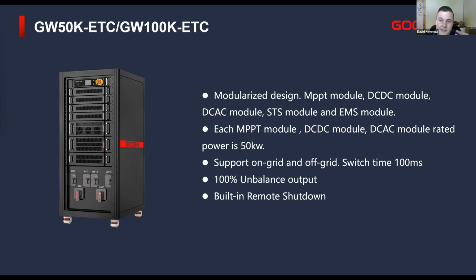These devices also have a lot of features and functionalities, from load management to that peak demand that I was mentioning earlier. We know that when customers are billed on kVA, that spike in peak demand normally increases their bill immensely. These devices are being designed to have that kVA compensation, so that even if you are saving your batteries for outages, it will use the batteries momentarily to mitigate that kVA demand and increase customer savings.